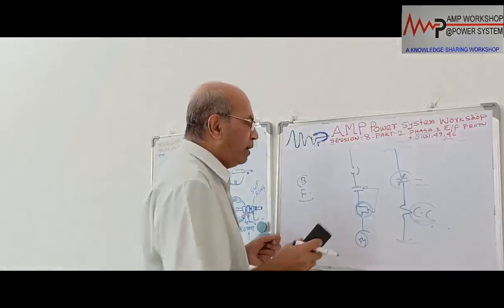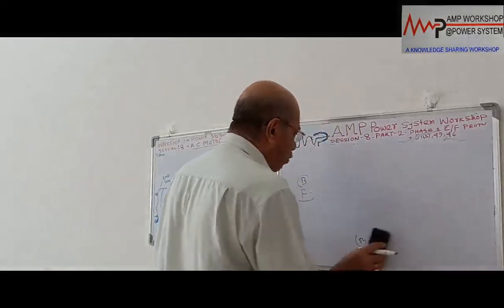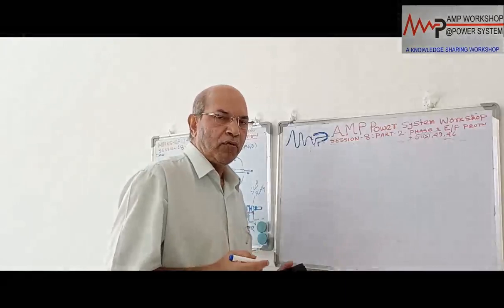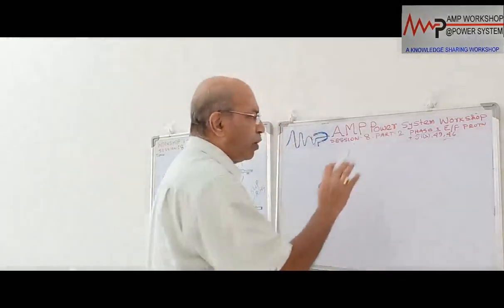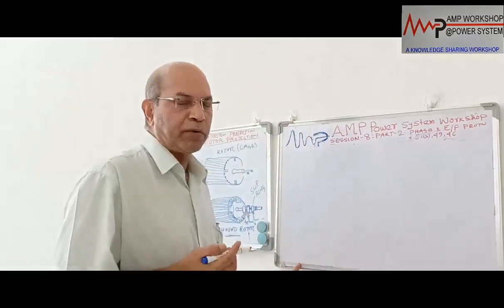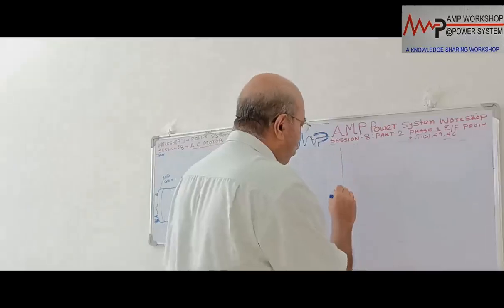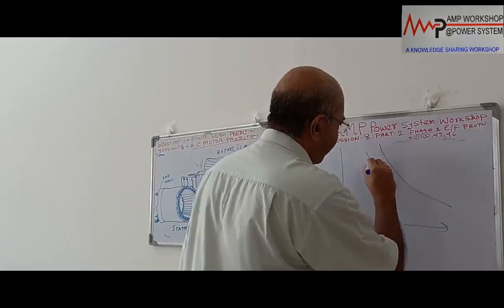Okay. But for a big motor, normally we can provide it in two ways. One way is provided by the relay itself. The overcurrent relay which we are using, we can use a long IDMT overcurrent relay. Suppose when we go for the overload protection or the temperature rise protection of the motor, we have to consider two curves of the motor. We already said the motor has two curves. We call them the cold curve and the hot curve.